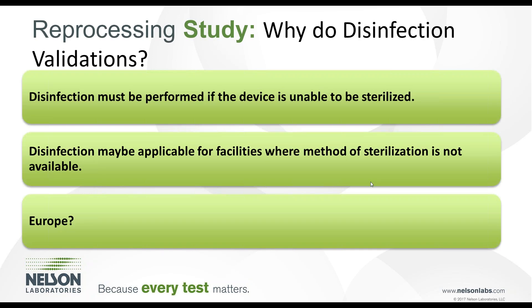So what is disinfection? Disinfection is defined by the killing of a specific level of organism, depending on the level of disinfection, and rendering the device free of those organisms so it's safe to handle for the person using the device on the patient or processing it for the next reprocessing step. Disinfection is typically done on devices that either cannot be sterilized or don't require sterilization, and one big difference between the U.S. and Europe is when disinfection is required.